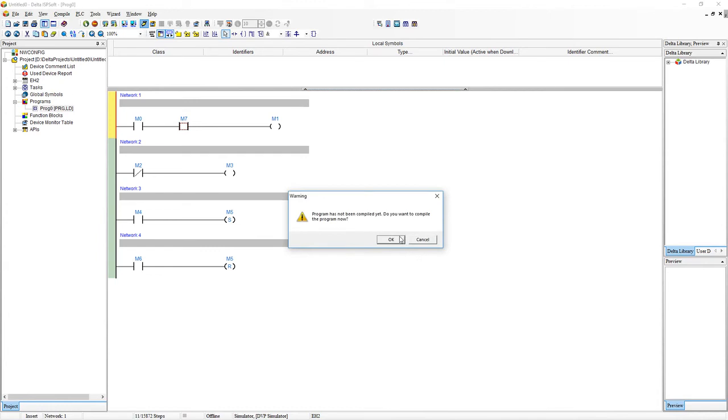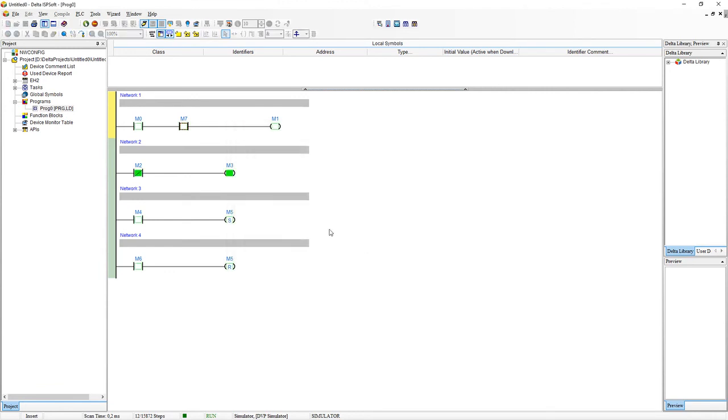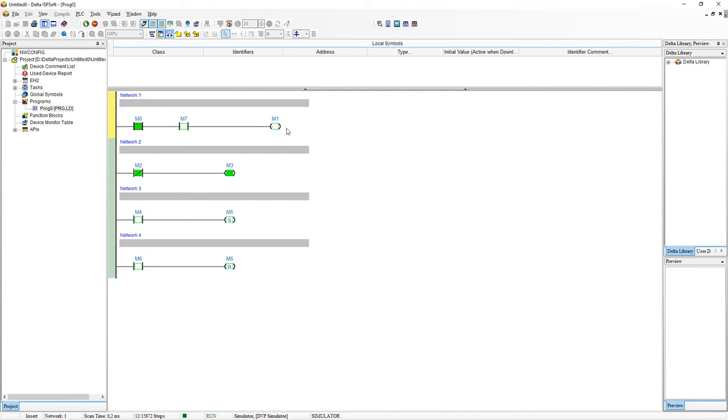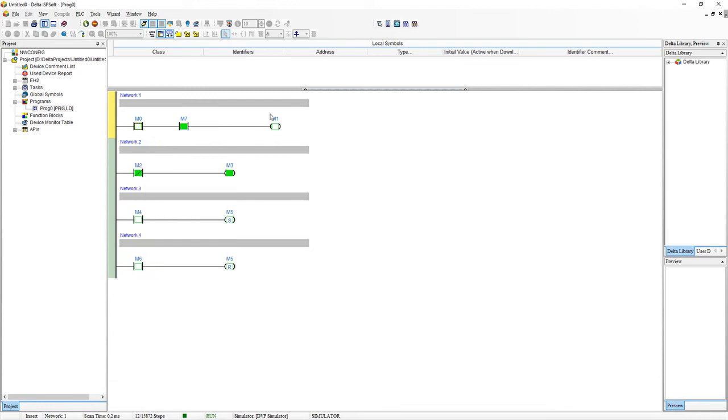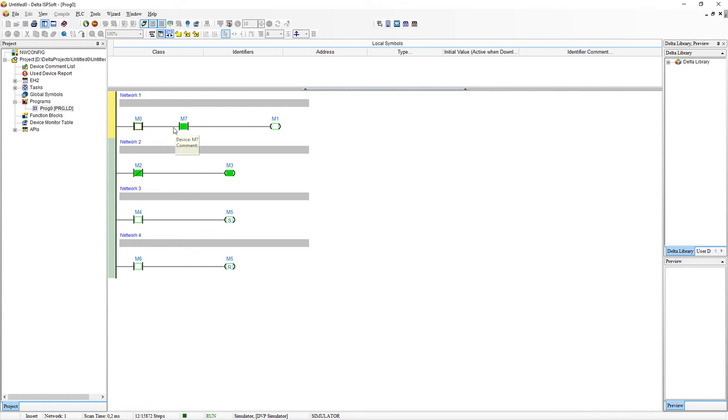So now basically M0 and M7 needs to be on for M1 to be on. So again go into online mode and test this. Set that on so you'll see M1 is still not on until M7 is on and then M1 will energize. If M0 is off it will also not energize so therefore these two need to be on. For your conventional programmers what has happened here is we had LD M0 and M7. So that would have been your if condition for those two bits to be on or true for M1 to be true.